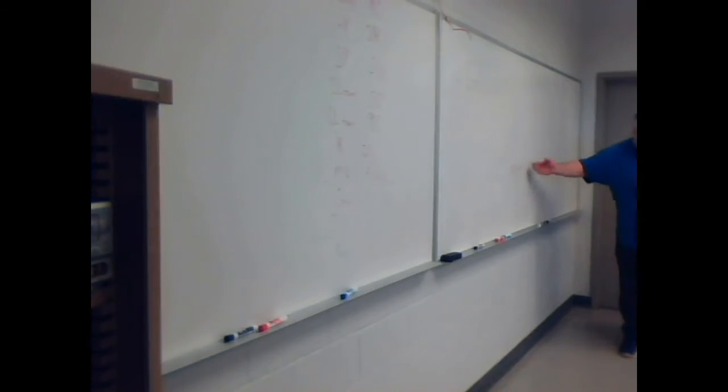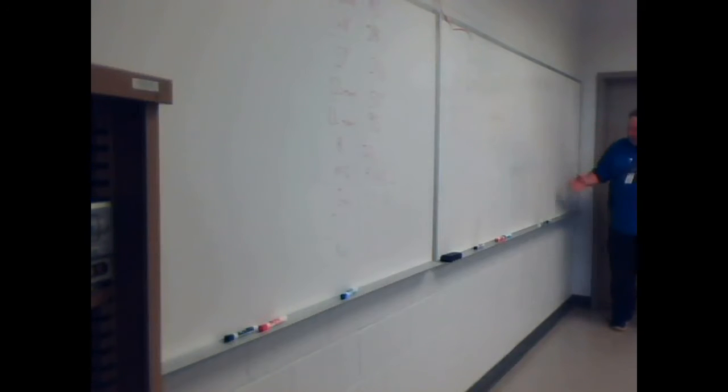If this is 100% vapor, it can't change to more gas. It's already all gas. So if I add anything else to it, it's going to go up sensibly. And that's superheat. We've already changed all this to a liquid. It can't change more to a liquid. It's all a liquid. And if I remove anything else from it, it subcools sensibly.